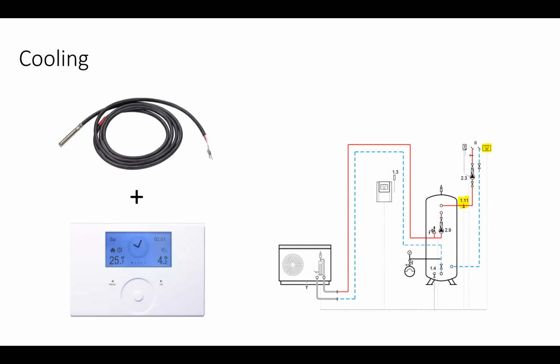Anyone considering doing floor cooling, do your research, go into it knowing what you're talking about. We're talking a heating system, generally speaking, with standard 200 mil spacings. We don't want to go too hot, but normally we're talking 80 watts per square meter or so is our distribution, how much heat we can punch out. Cooling, with the same installation, you might be looking at 25 watts per square meter. Now, is 25 watts per square meter enough?